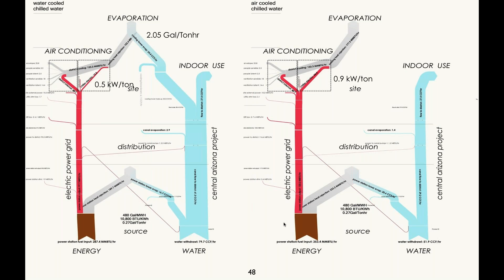All right, that was my little Sankey diagram. So another trend we're seeing is if you look at the ratio of water cost to electric energy cost in a chiller plant. This graph gives you an idea of what those costs are for a 1,000-ton plant. Certainly the air-cooled plant doesn't care, independent of water, but a water-cooled plant, the higher the water cost, the more overall cost that's going to induce.